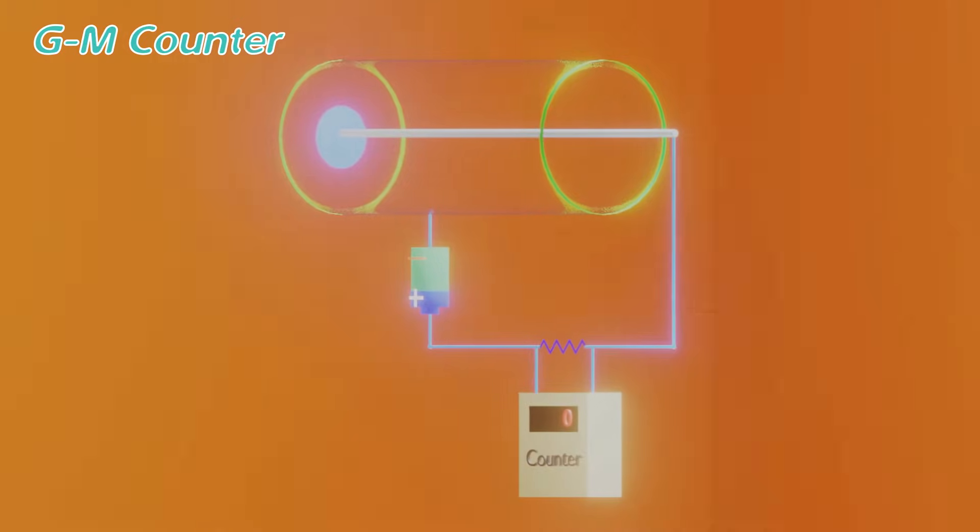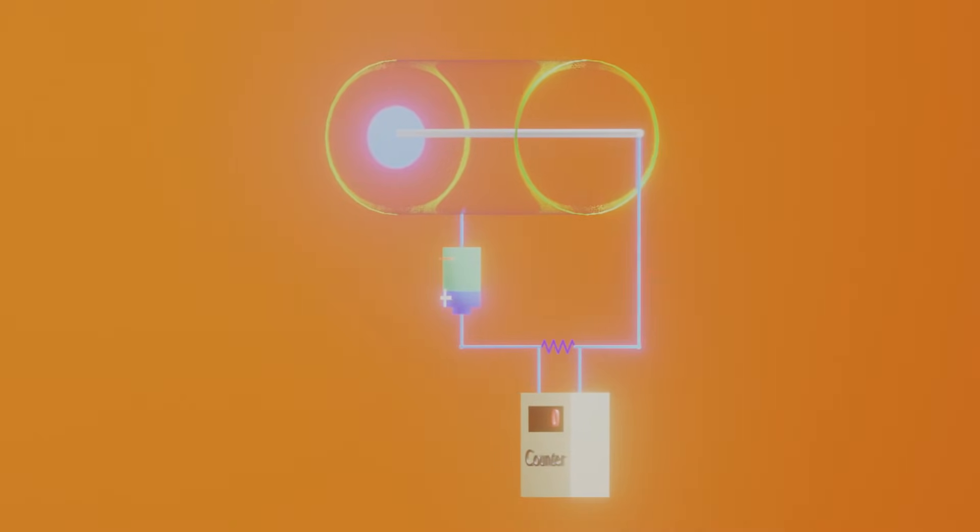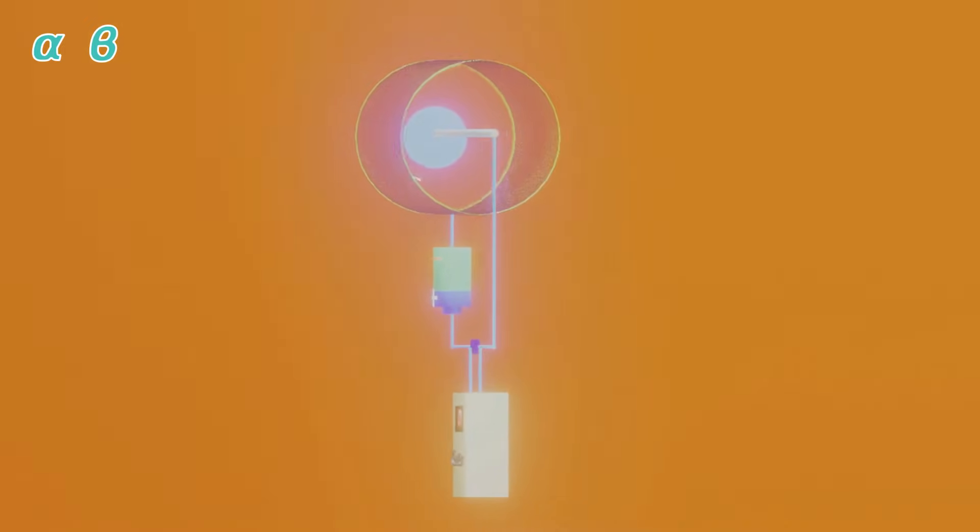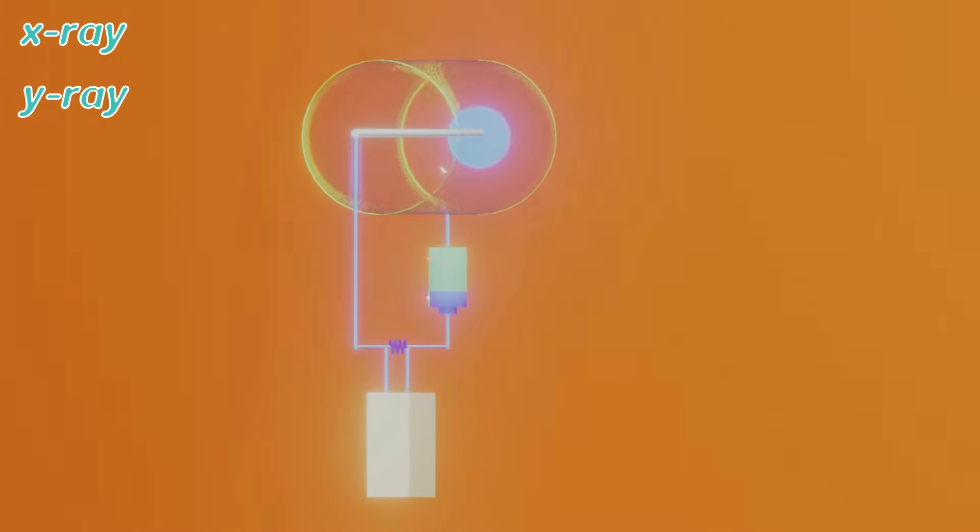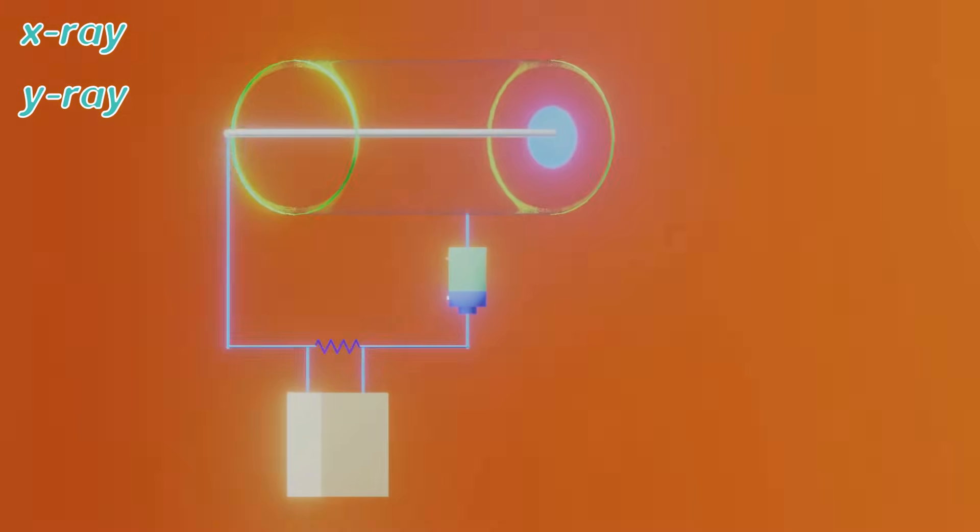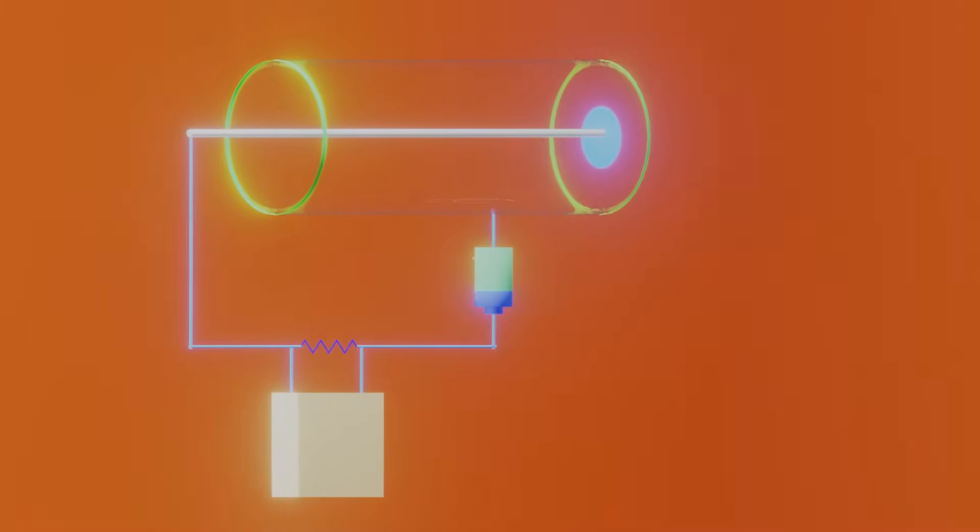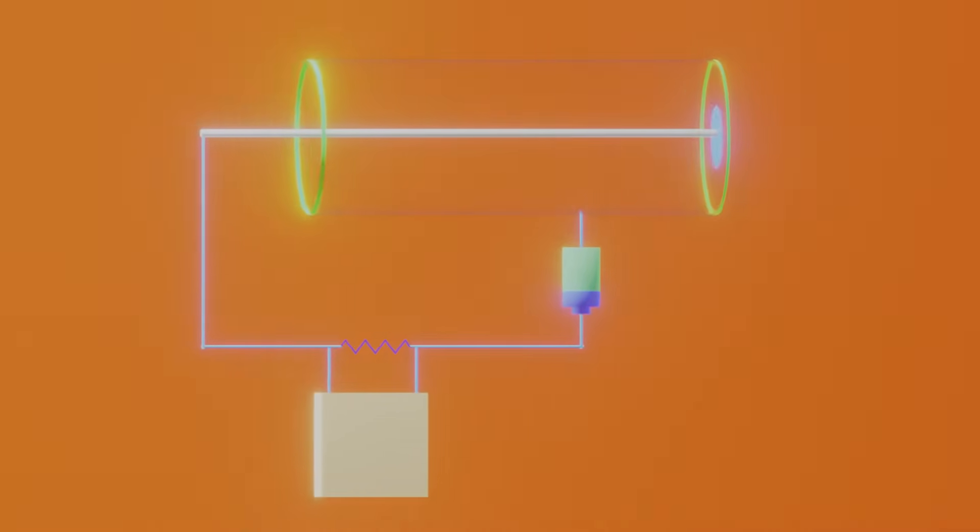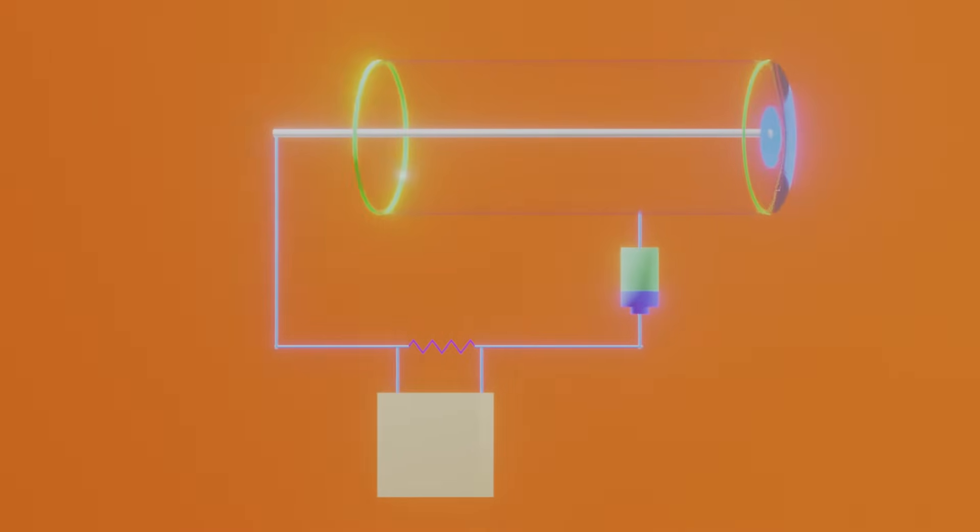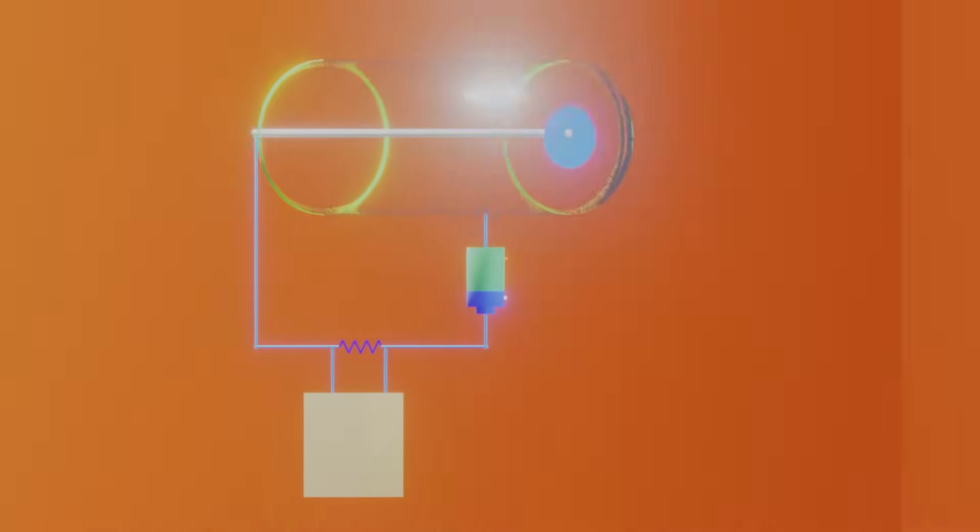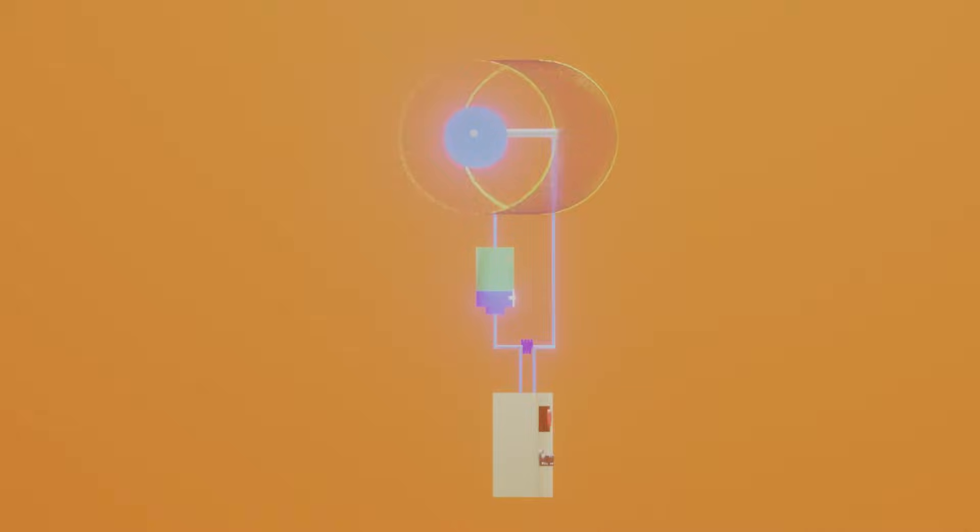So it can detect charged particles like alpha and beta, and uncharged radiations like X-rays, gamma rays, etc. The charged particles directly ionize the gas, and the radiations produce secondary electrons which in turn produce ionizations.